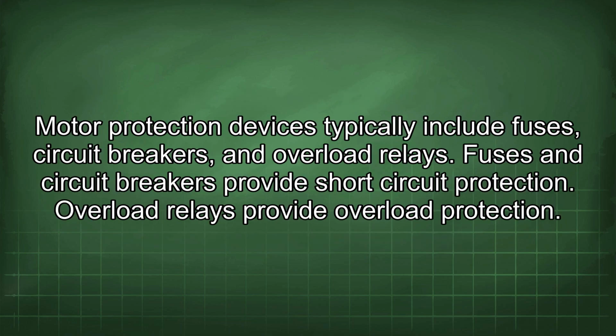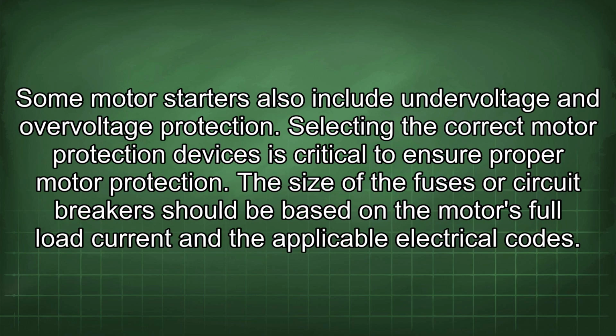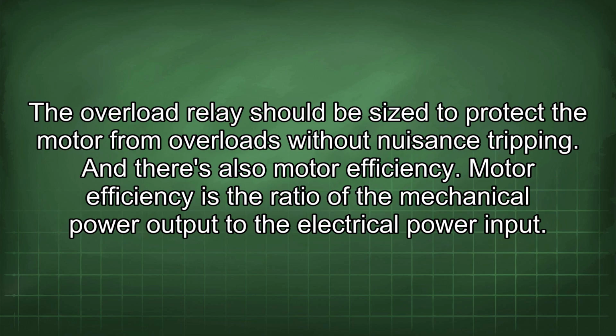Motor protection devices typically include fuses, circuit breakers, and overload relays. Fuses and circuit breakers provide short circuit protection. Overload relays provide overload protection. Some motor starters also include undervoltage and overvoltage protection. Selecting the correct motor protection devices is critical to ensure proper motor protection. The size of the fuses or circuit breakers should be based on the motor's full load current and the applicable electrical codes. The overload relay should be sized to protect the motor from overloads without nuisance tripping. And there's also motor efficiency.